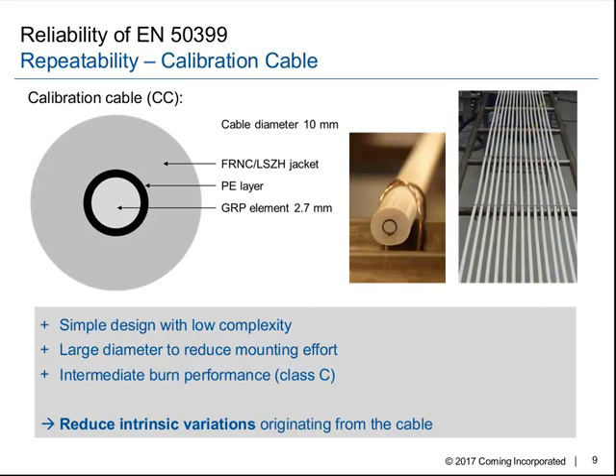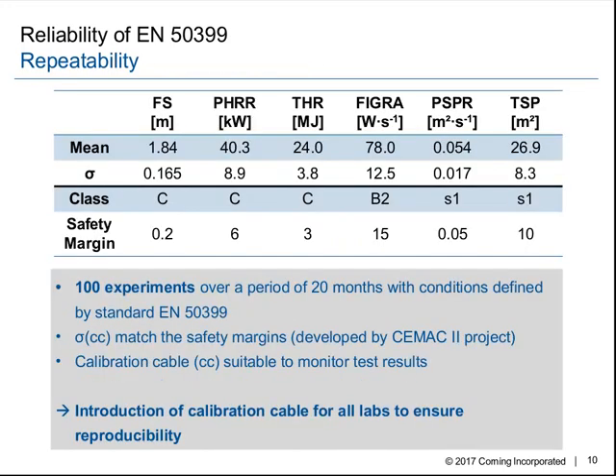With this cable, we wanted to test the repeatability. So what we did is we burned this cable 100 times over a period of 20 months, always with the same conditions as defined by the standards. What you can see here is the mean of those 100 experiments for each of the parameters. The first thing we see is that the flame spread of the calibration cable is somewhere halfway up the ladder. So this is exactly what we were aiming for.